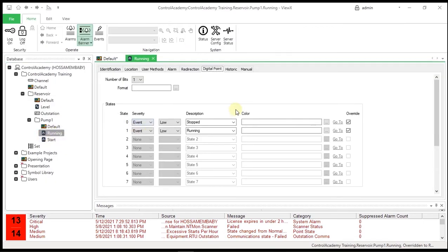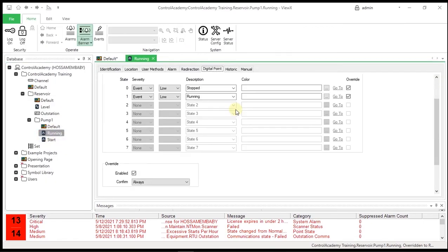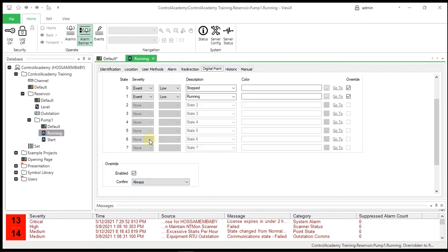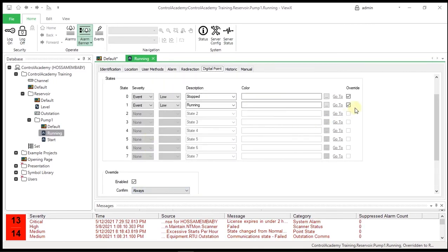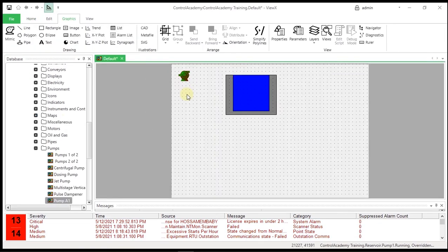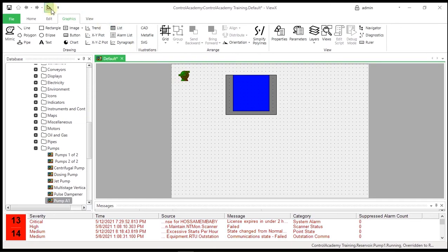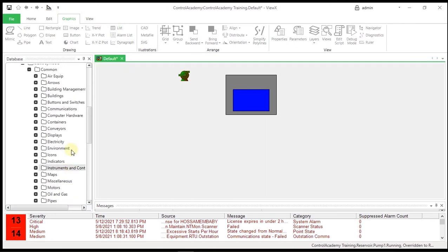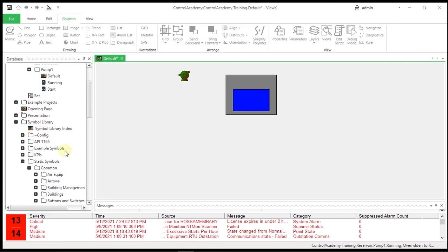It's important to make sure that you enable Override property in your internal point. Now put the Mimic in Run mode and verify that the pump changes color when you toggle the running point.